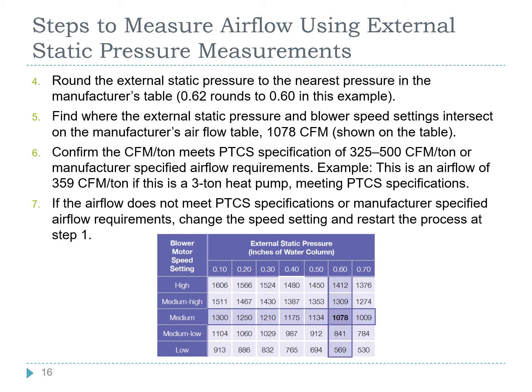Now, to confirm the CFM per ton meets the PTCS specification of 325 to 500 CFM per ton, or the manufacturer specified airflow requirements, we would take that 1078 and divide it by the tonnage of the outdoor unit. In this example, we're going to use 3 ton, and that would result in a CFM per ton of 359 CFM per ton, meeting the PTCS specifications. If the airflow does not meet the specification or the manufacturer's specified airflow requirement, you can change the blower speed and start this process over at step 1.